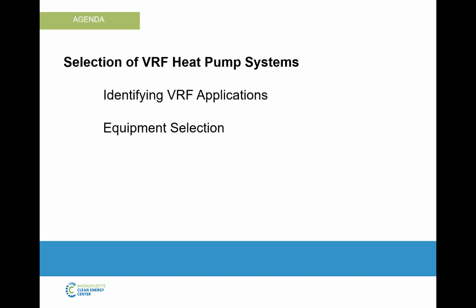So I typically try to push people more towards dollars per square foot for an average zone building rather than dollars per ton, because your tonnage is going to change quite a bit depending on how good the construction is in that building. Whereas I find the biggest indicator of cost is usually zoning, and zoning is pretty loosely related to the actual square footage of the building. So for a really well-zoned simultaneous heating and cooling VRF system, you're probably looking at $28 to $30 a square foot, but it could be all the way down to $20 a square foot if you're using a changeover system, more reasonable zoning, a more simple system.